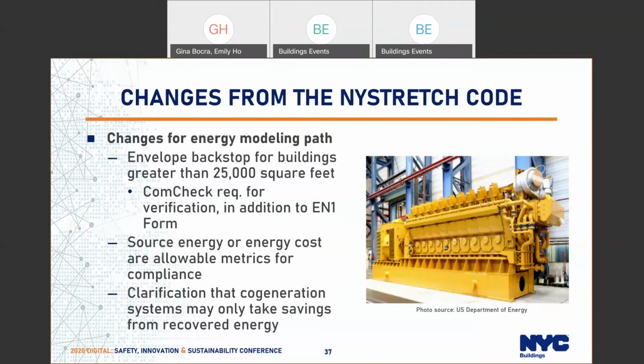But there's a COMcheck requirement for verification, and it says, essentially, if you have a Group R building, your envelope cannot be 15% worse than the prescriptive requirements in the code. If you have any other occupancy type, it cannot be more than 7% worse than the minimum prescriptive code requirements for compliance. So you can still have an envelope that doesn't meet the prescriptive requirements of code and trade it off with HVAC and lighting, but you have a threshold now on how bad that can be. So that's one major change.